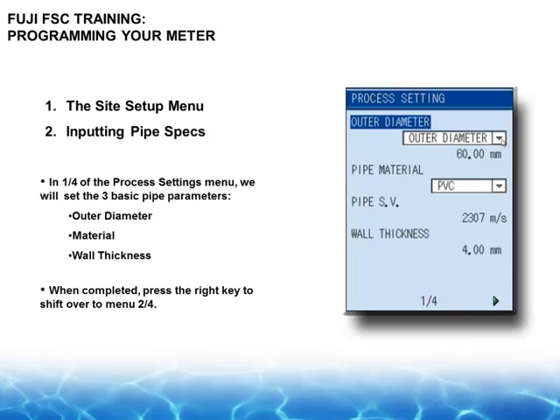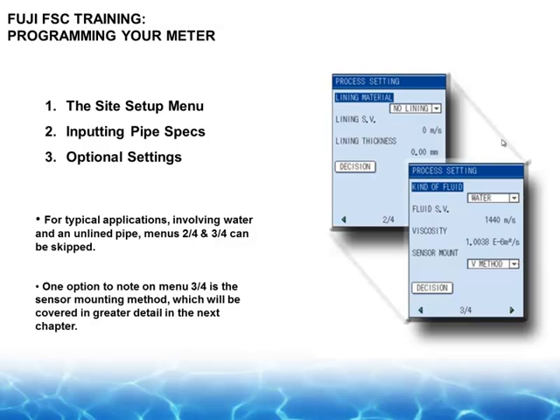We do have ultrasonic thickness gauges. Again, they're optional and usually don't serve a purpose because the thickness gauges will measure the paint thickness, and they may measure if you have any metallic buildup inside the pipe, like rust. They will not measure any soft gooey stuff or any calcium type of buildup on the inside of the pipe. So for the most part, the ANSI pipe chart book is usually more than sufficient for most flow survey applications. So we put that data in. If you have a liner, you need to put in the liner information, like your mortar lining and so on. Then we need to select the flavor of your liquid. Most of the time, again, you will be putting in water. The reason being, the technology has evolved from the days of your old Controlotron meter 10, 20 years ago.